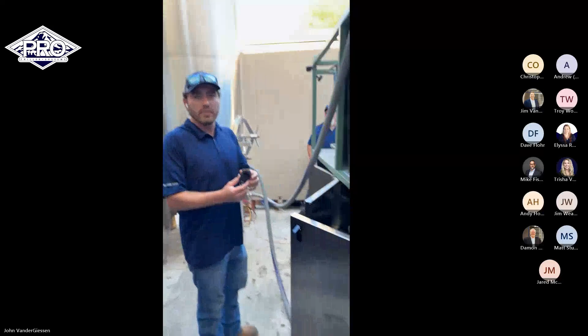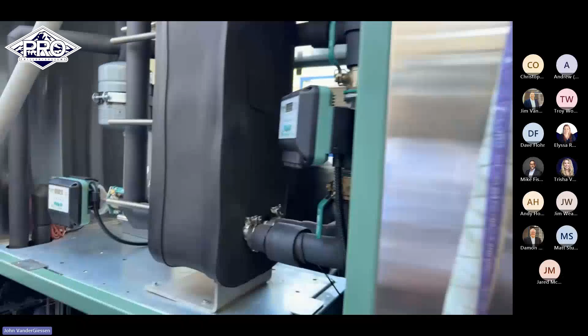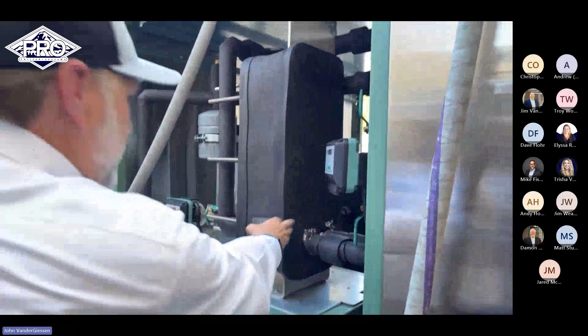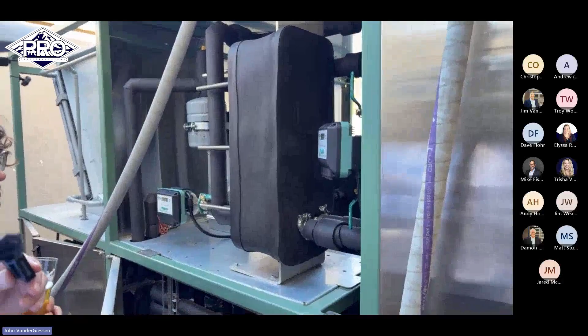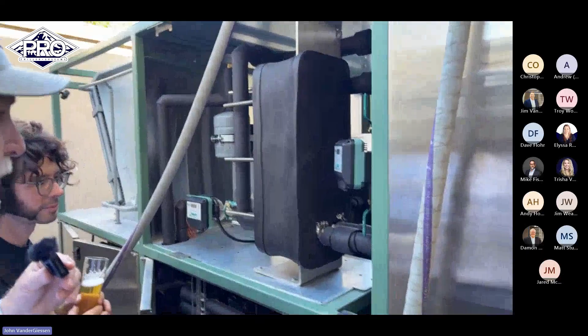Okay. Yeah, this is the heat recovery. This is our waste heat recovery section here. This was the first unit, and this is now offered as an upgrade on all of our systems. But we're using a Thermaline gasketed plate heat exchanger for our secondary heat exchange. So we're heating all of our potable hot water with a gasketed heat exchanger that you can open up and clean and access. And a lot of our customers have real harsh environments, and this just gives you that buffer and protection. And then we have an internal, we call it our recovery glycol loop. And then that glycol loop is what we circulate against the refrigerant.